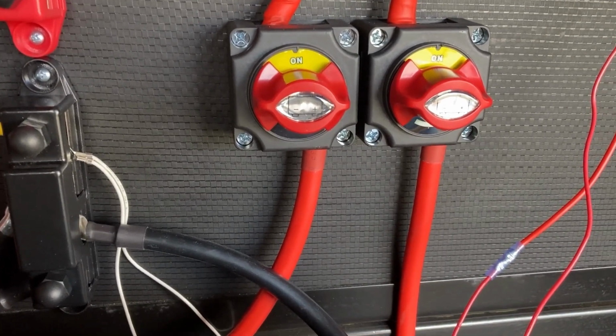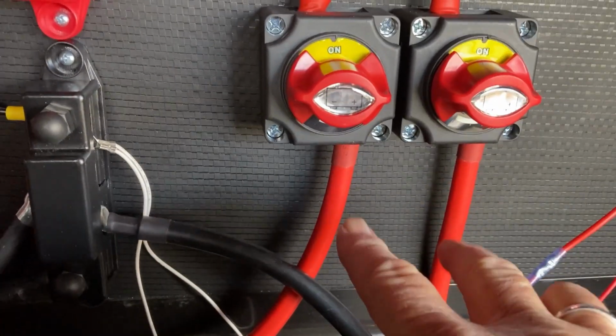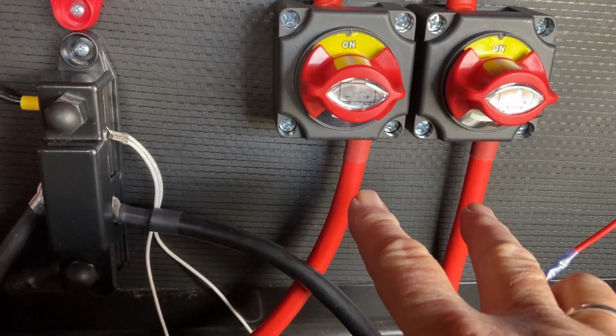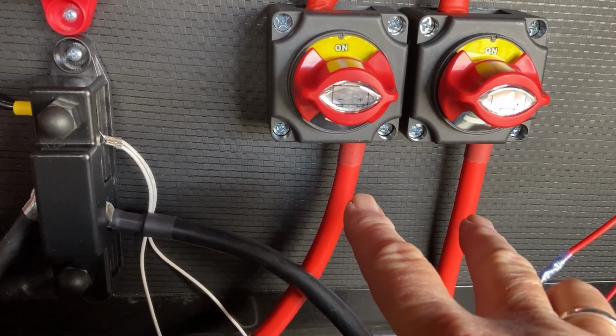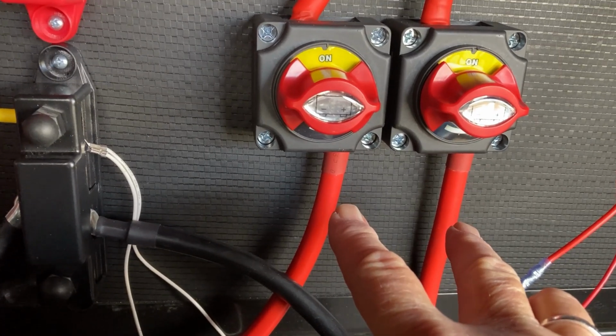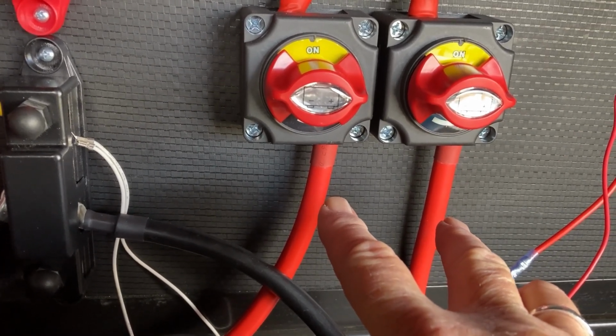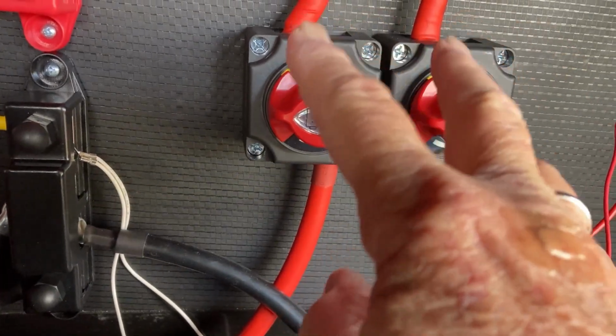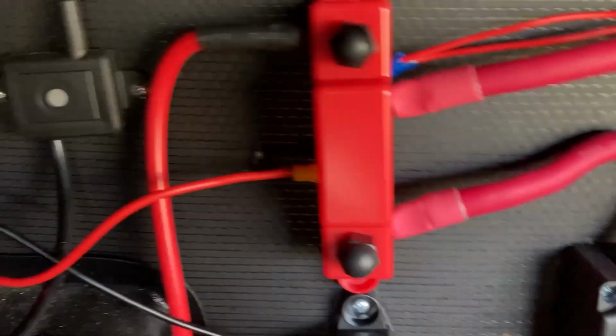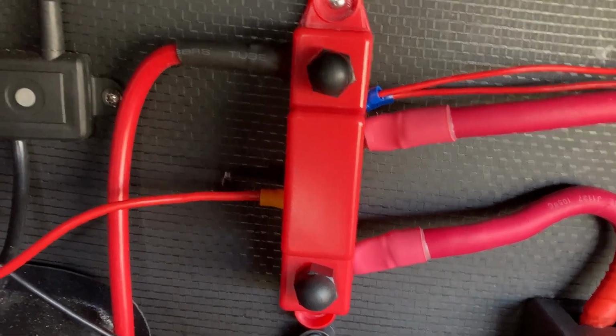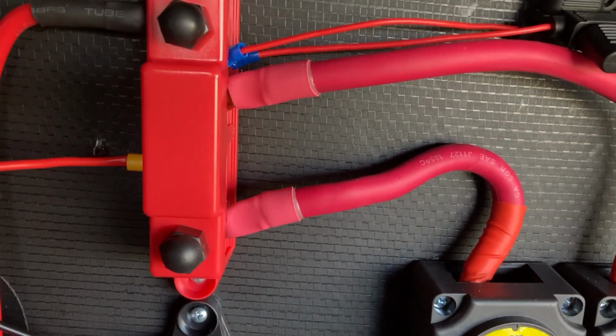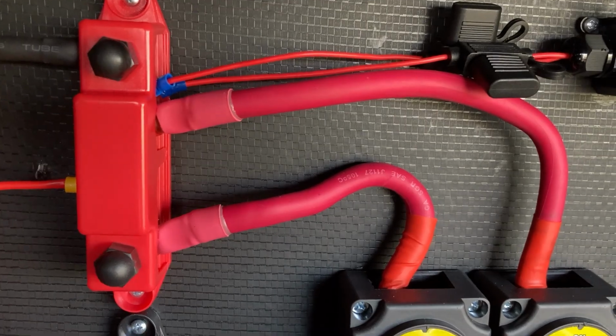Now, one thing I'll tell you is about these battery wire sizes—let me give you a little rundown on that. These cables you see coming in to the bottom are coming from the batteries. Those are 2 AWG cables, size 2-aught, okay—big, but they can handle high amperage. Coming out at the top is also 2 gauge, going into the bus bar. Those are 2 gauge cables—huge, and a little more expensive, but they can handle high amperage.